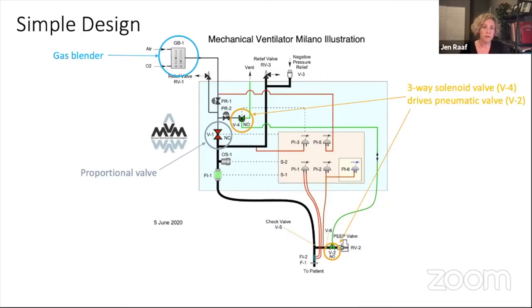The valve circled in yellow at the top is a three-way valve that drives this other valve down at the bottom. It decides to open or close the bottom valve at the appropriate time in the breathing cycle to allow the patient to exhale.